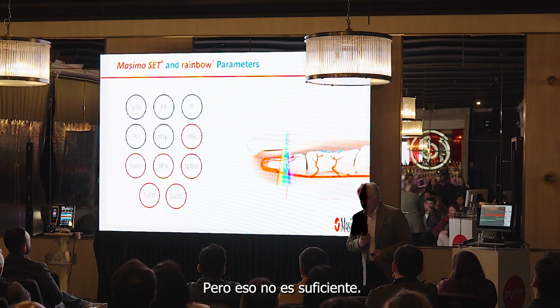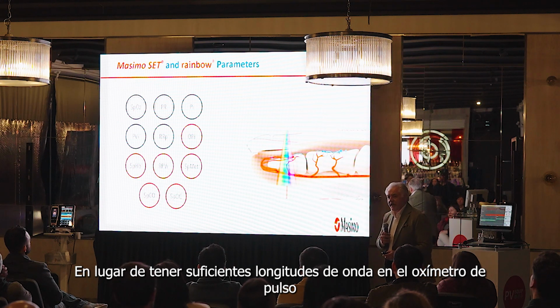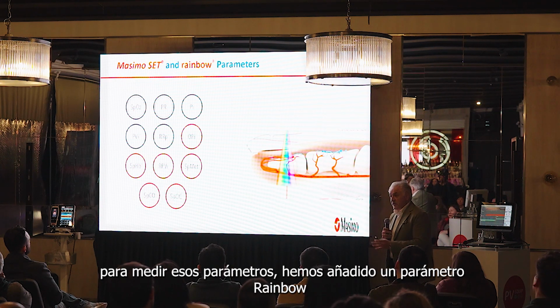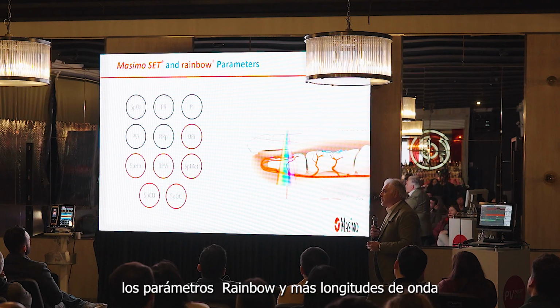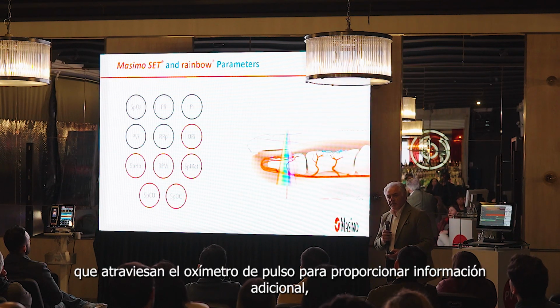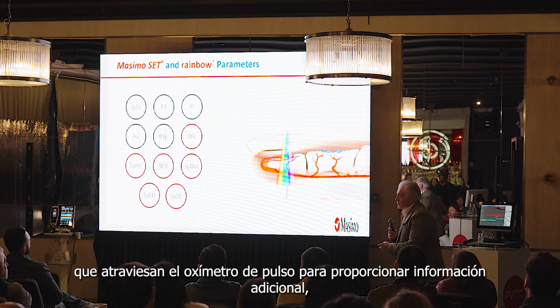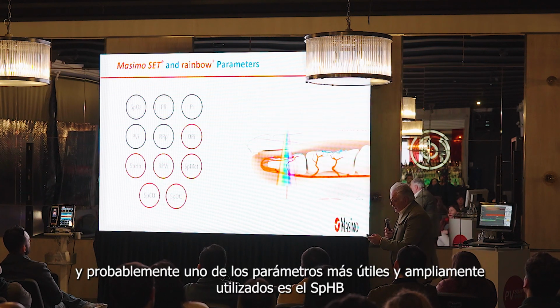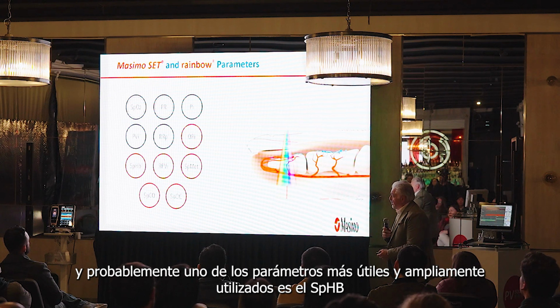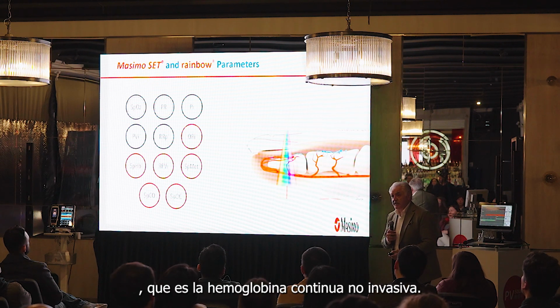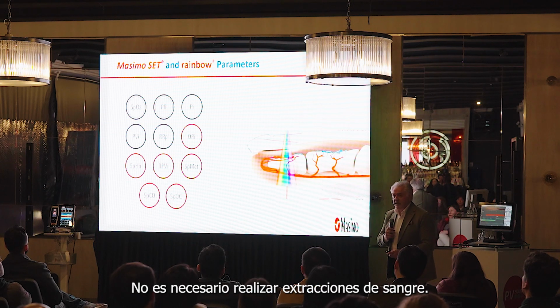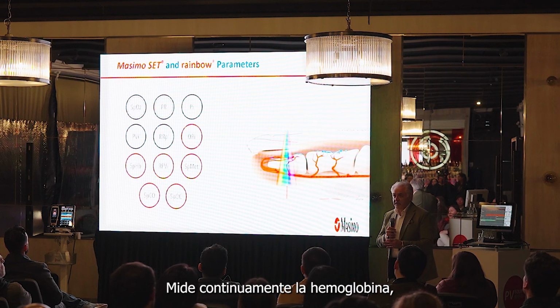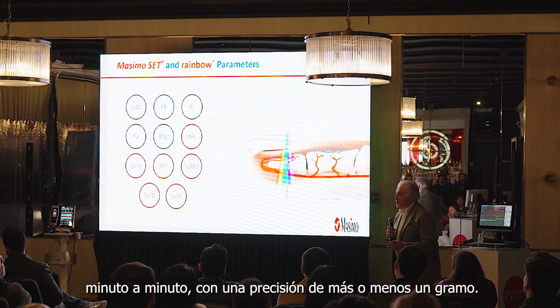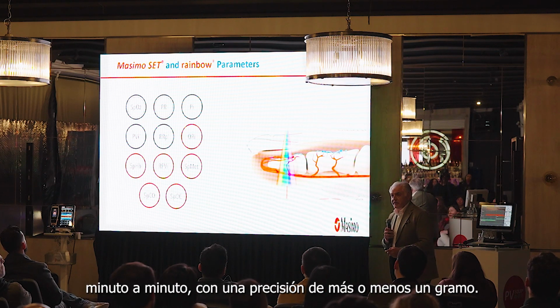That's not enough, okay? So instead of having just enough wavelengths in a pulse oximeter to measure those parameters, we added rainbow parameters. The rainbow parameters are more wavelengths going through the pulse oximeter to give you additional information. Probably the two most useful parameters that are widely used are SpHb, which is continuous non-invasive hemoglobin. You don't have to do blood draws. It continuously measures the hemoglobin minute by minute, plus or minus 1 gram accuracy.